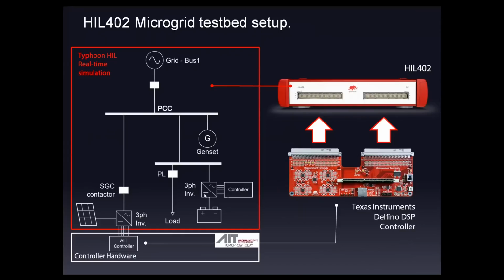On top of that, we'll also have a 3-phase battery storage inverter that is controlled with the controller inside the HIL simulation environment. And this is a very new, very interesting development in our latest software release, where now you can model inside the real-time simulation not just the power stage, but you can also model equally well the signal processing and the control part. So basically your inverter can be controlled from the real-time simulation. So in a way we have a hybrid system. We have a controller in the loop, that's the Delfino, and we also have the controller inside the simulation, plus all the models of the genset, transmission lines, protective relays, and so on.